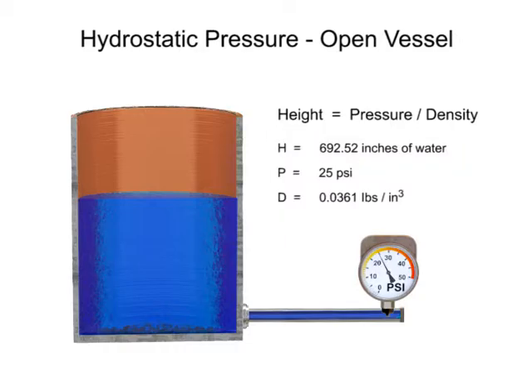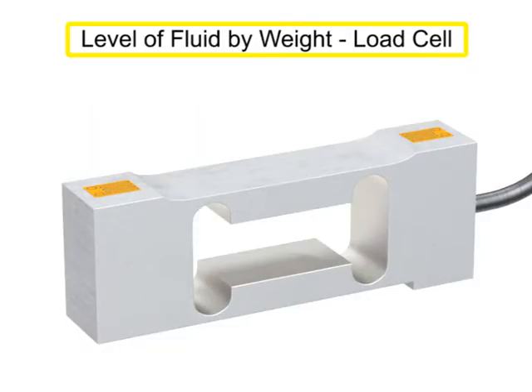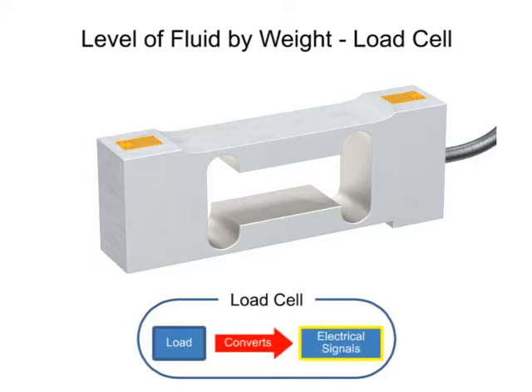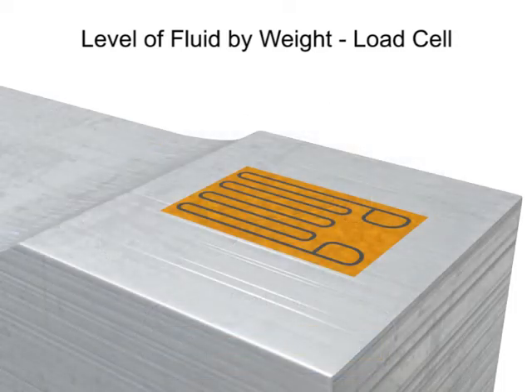Another method of calculating the level of material in a vessel by weight is using load cells. Load cells are comprised of a strain gauge bonded to a support and convert a force or load to an electrical signal. As force or weight is applied to the load cell, the strain gauge deforms and causes the electrical resistance to change.